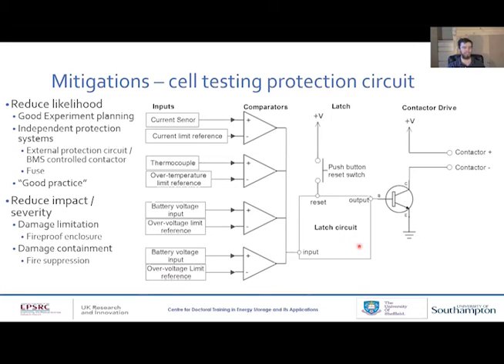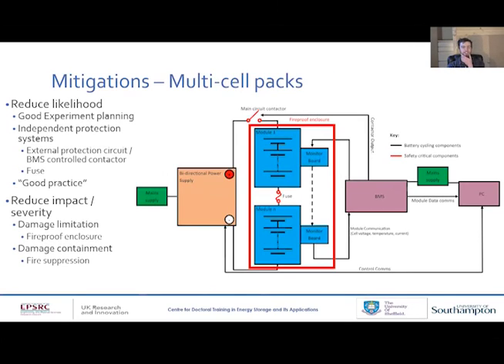That then feeds into a latch circuit. So if one of the limits is exceeded, it will open the contactor and it can't be closed again until the limit is no longer exceeded and an operator pushes a button, just for an extra level of safety. Then looking at multi-cell packs, again, pretty similar story, but instead of the protection circuit here, we're using that BMS to control the contactor.